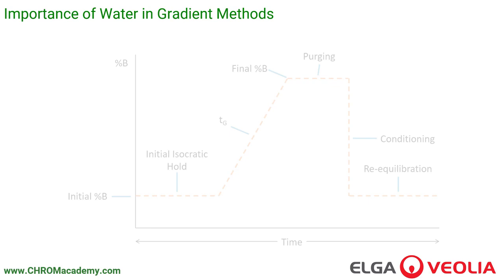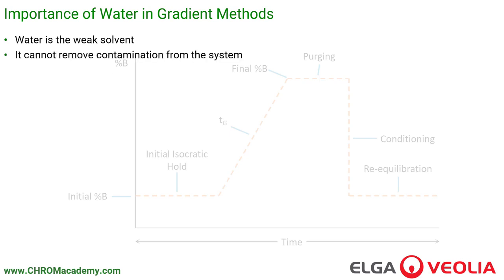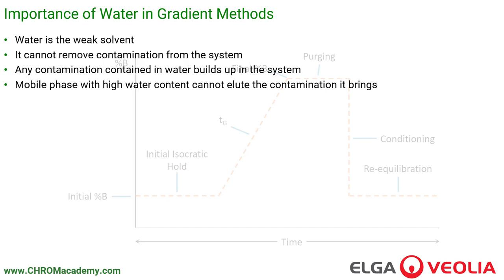When using gradient methods, it's important that we use very good quality water. Water is the weak solvent — it cannot elute substances that have any real degree of retention or affinity for the stationary phase, and it can't remove contamination from the system. Any contamination brought by the water into the system sticks to the column and builds up. The water itself cannot remove that, so the water is effectively contaminating the system because it simply isn't strong enough to remove any contamination that builds up.